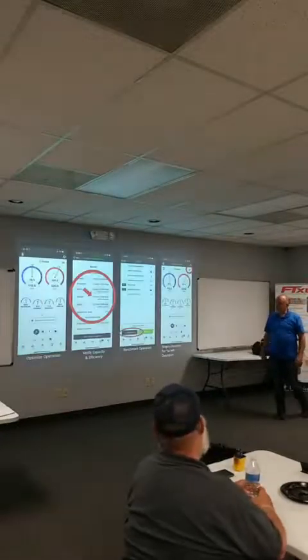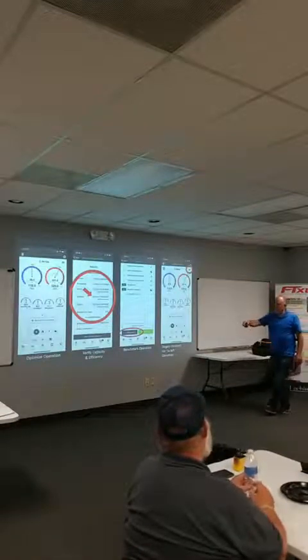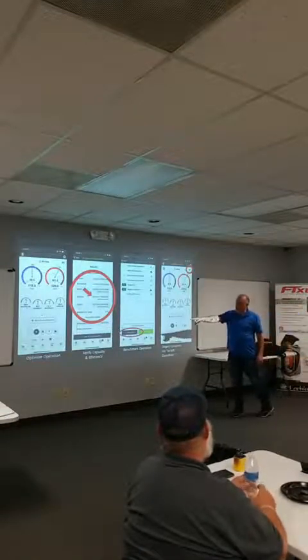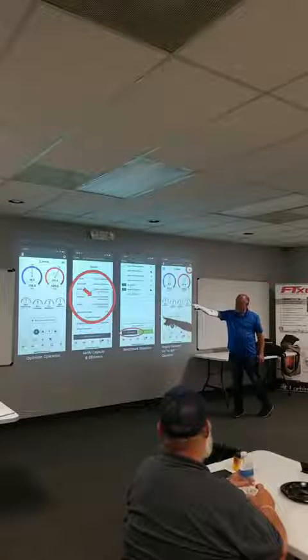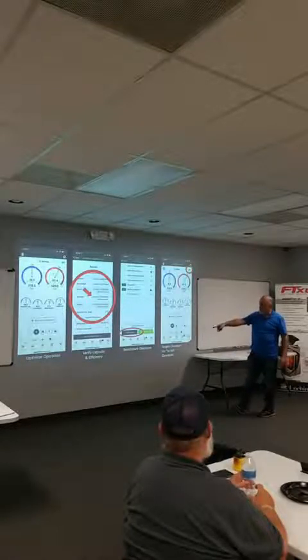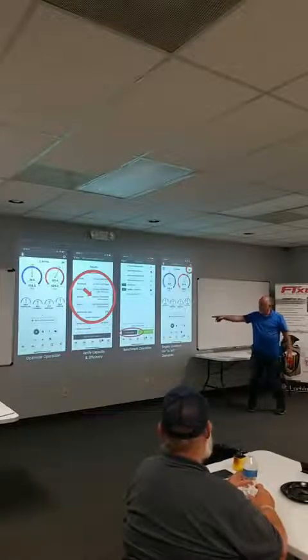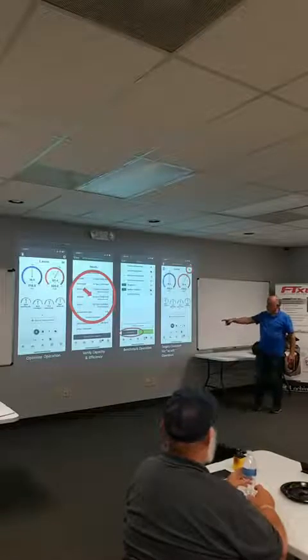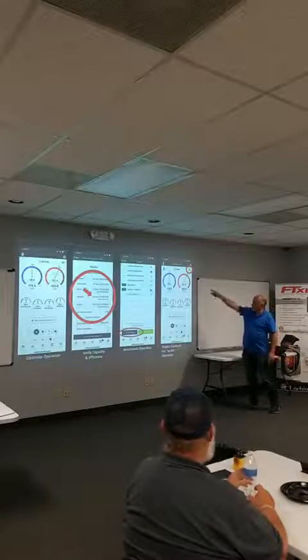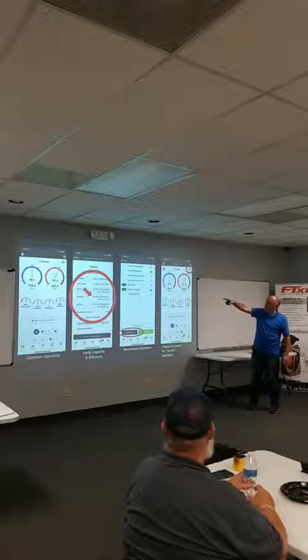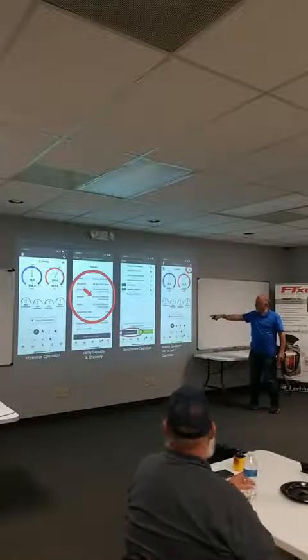So we're gonna use non-invasive going forward. What we're doing here is gonna optimize the operation, so you get everything in target zones, you get your tonnage correct, and verify your capacity. Down at the bottom there's a benchmark button, and all that does is lock these targets in. So you can see there, the pressures aren't exactly under the flags, and it's gonna lock this in.